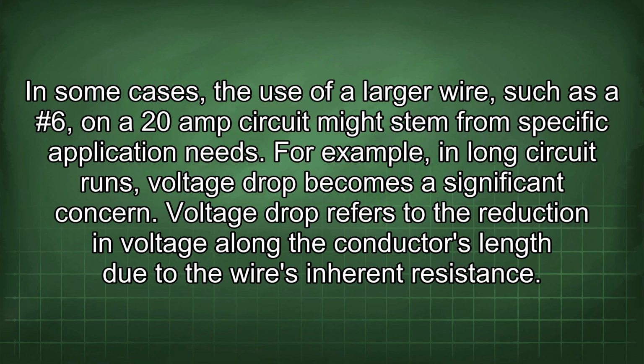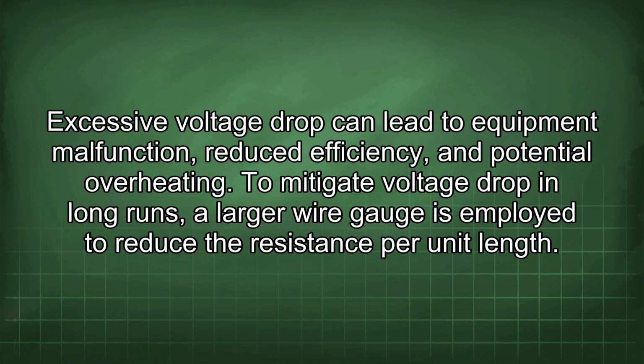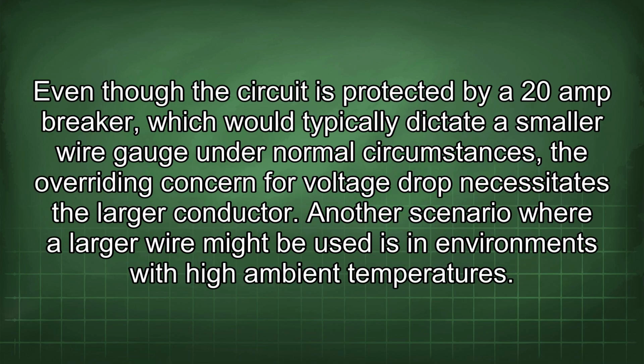Voltage drop refers to the reduction in voltage along the conductor's length due to the wire's inherent resistance. Excessive voltage drop can lead to equipment malfunction, reduced efficiency, and potential overheating. To mitigate voltage drop in long runs, a larger wire gauge is employed to reduce the resistance per unit length. Even though the circuit is protected by a 20-amp breaker, which would typically dictate a smaller wire gauge under normal circumstances, the overriding concern for voltage drop necessitates the larger conductor.